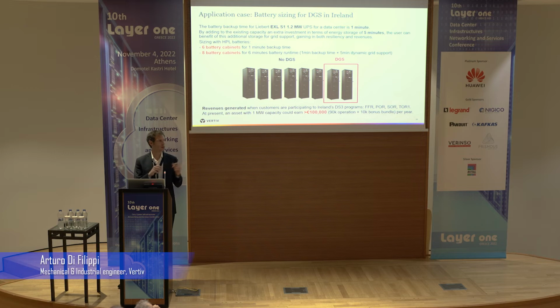You have a 1.2 megawatt load, and you want to guarantee battery runtime for 1 minute. You have 6 cabinets for the batteries. If you want to add the possibility to also work with grid services, for grid support, you can add 2 extra battery cabinets. You can extend the runtime to 6 minutes total: 1 minute for backup and 5 additional minutes for grid support.